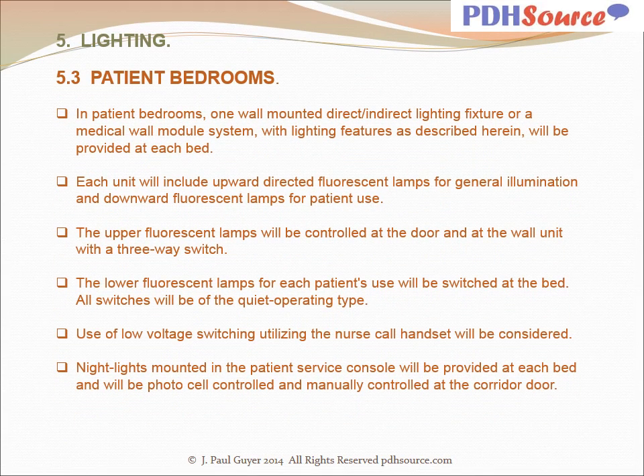In patient bedrooms, one wall-mounted direct-indirect lighting fixture or a medical wall module system with lighting features as described herein will be provided at each bed. Each unit will include upward-directed fluorescent lamps for general illumination and downward fluorescent lamps for patient use. The upper fluorescent lamps will be controlled at the door and at the wall unit with a three-way switch. The lower fluorescent lamps for each patient's use will be switched at the bed.